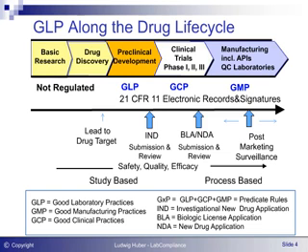Typically, research and drug discovery are not regulated at all. GLP starts with preclinical development, for example with toxicology studies. Clinical trials are regulated by good clinical practice regulations, and manufacturing through GMPs — good manufacturing practice regulations. There is a frequent misunderstanding that all laboratory operations are regulated by GLP, including quality control laboratories in manufacturing. This is not true; QC labs are regulated by GMPs, not GLPs. Also, 21 CFR Part 11 applies to all FDA-regulated industries, including GLP, GCP, and GMP, covering electronic records and computer systems.